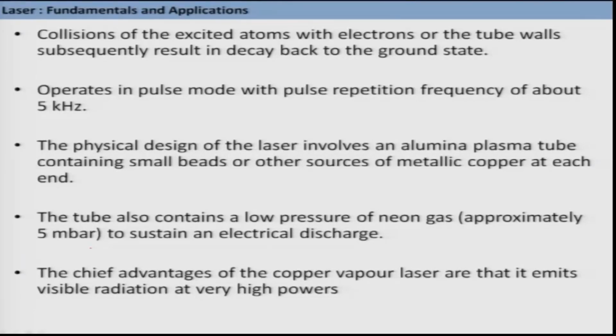How do you design this laser? The physical design involves an alumina plasma tube containing small beads, or other sources of metallic copper, and this tube also contains a low pressure of neon gas, which is kept at approximately 5 millibar, which helps to sustain the electrical discharge.